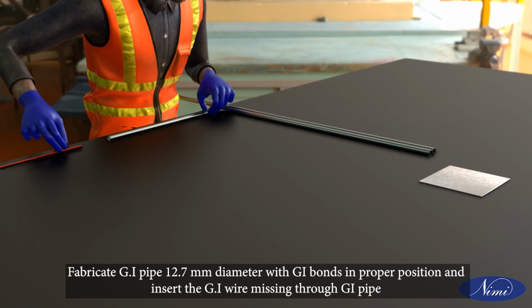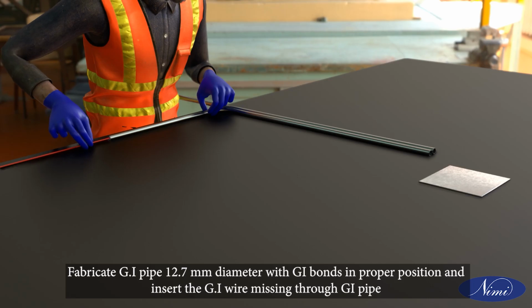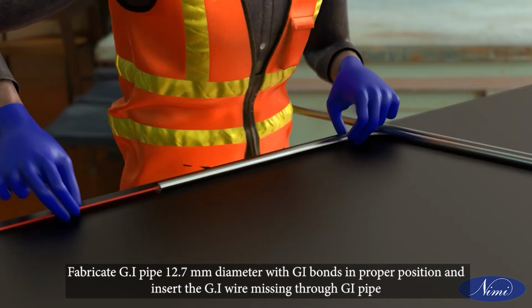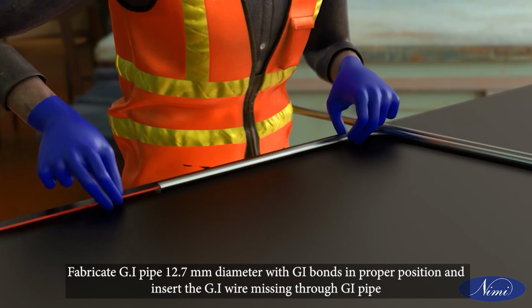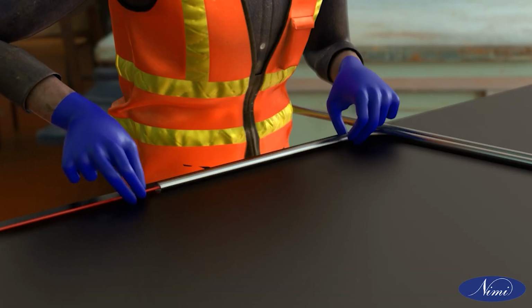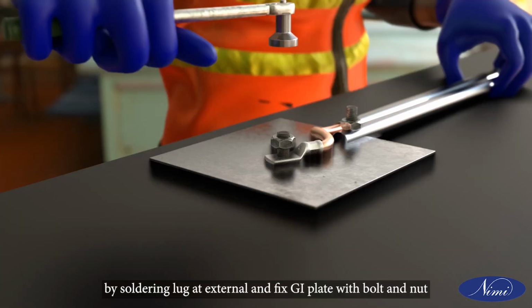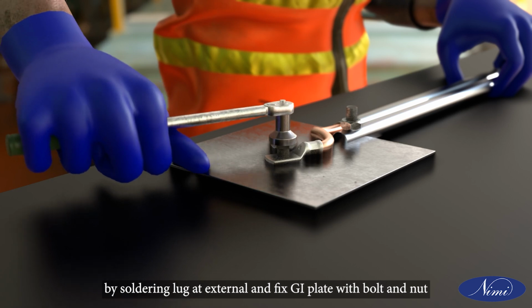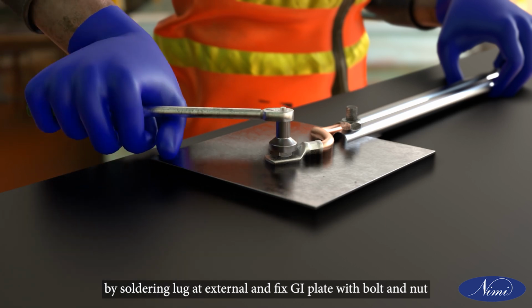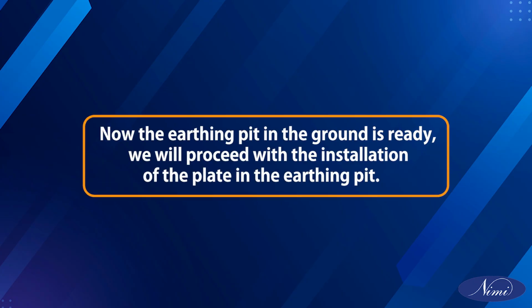Fabricate GI pipe 12.7 mm diameter with GI bend in proper position and insert the GI wire through the GI pipe, soldering the lug at the external end, and fix the GI plate with bolt and nut. Now, the earthing pit in the ground is ready. We will proceed with the installation of the plate in the earthing pit.